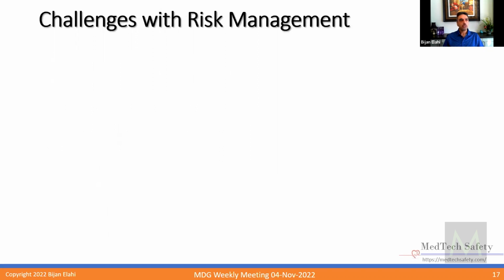I'll now touch on some challenges with risk management. One challenge is about all hazards and harms. We are required to consider all hazards and harms related to a device. And the word all is the challenge. How do you know you haven't missed anything? This is really like asking for perfection. And real life has a habit of surprising even the best of us.